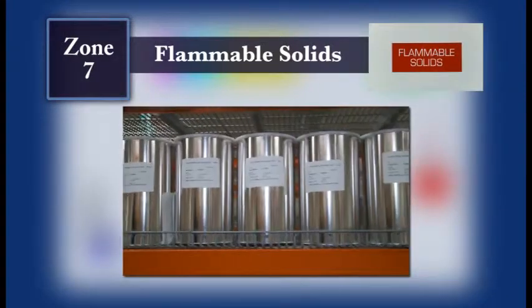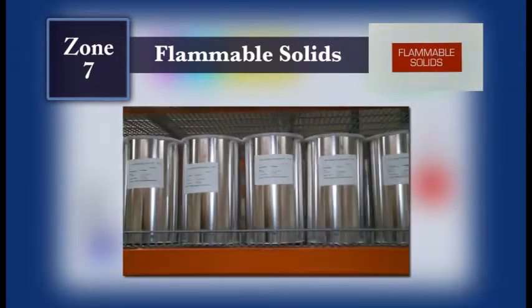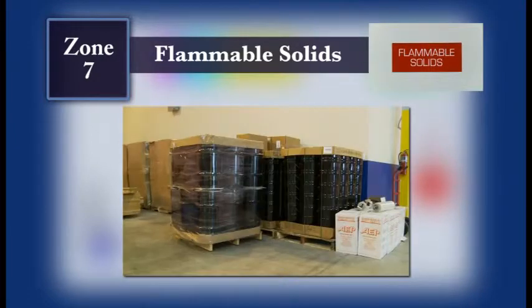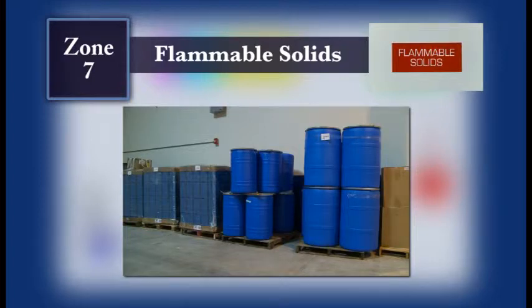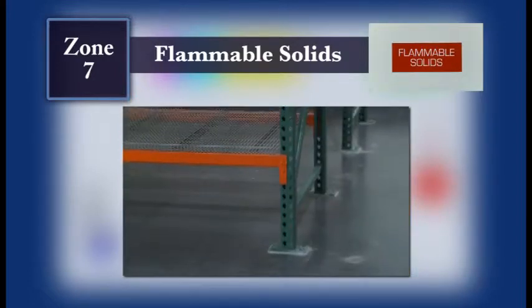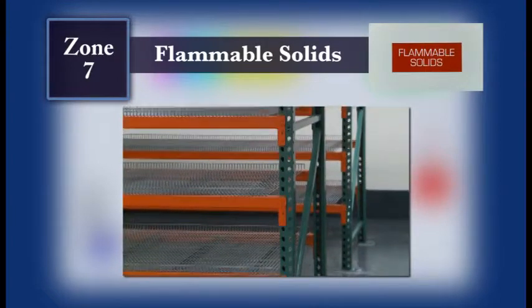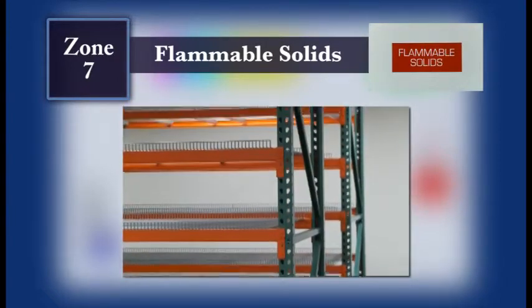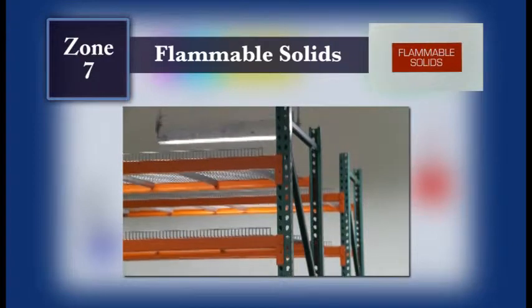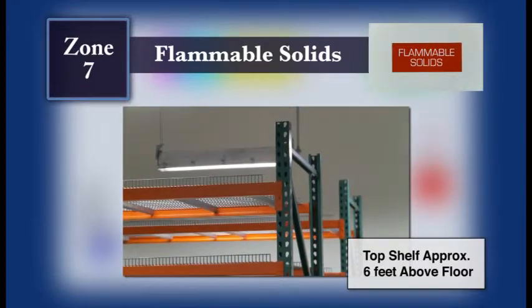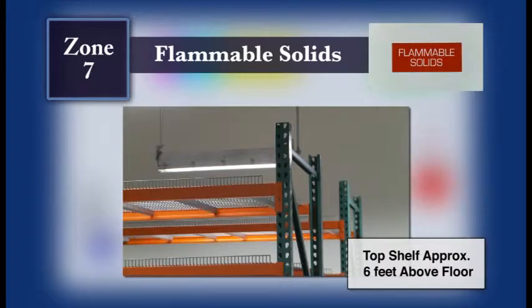Product stored in this area is primarily metal powders and chips stored in cans, metal pails, and drums that vary in size up to 55-gallon drums. It is restricted to materials that do not react with water or have a very low reaction if in contact with water in the liquid state. Product is generally located on wooden pallets or wire rack system. The racks are installed to create a space between each rack. Rack height varies based on height limitations imposed by structural and other systems, but generally is 3 or 4 levels high. The elevation of the top level is approximately 6 feet above the finished floor.